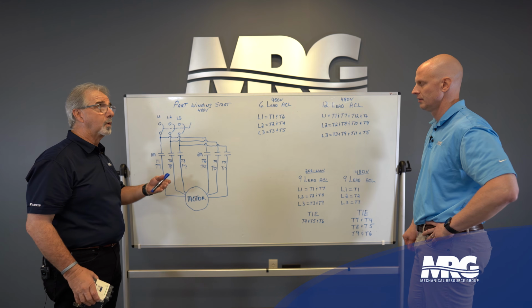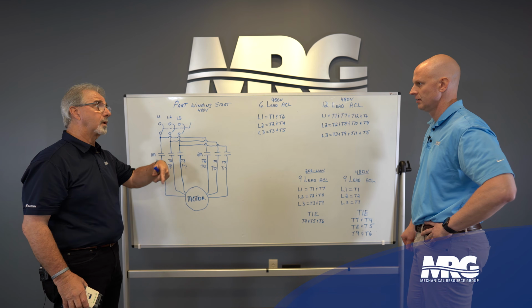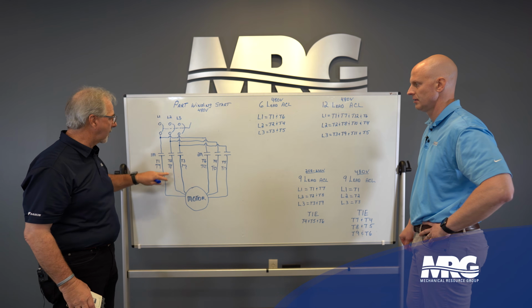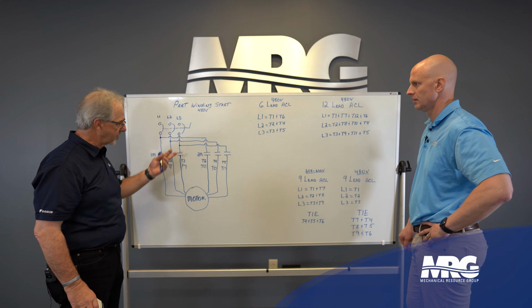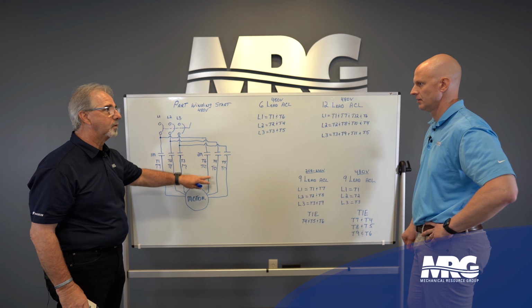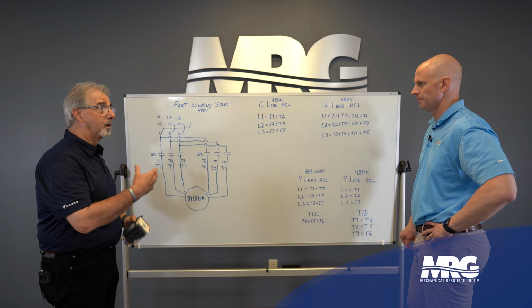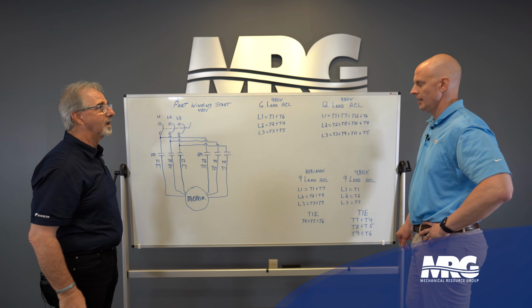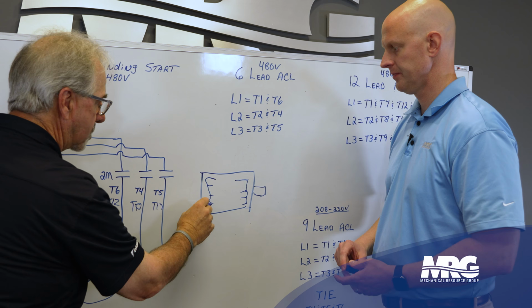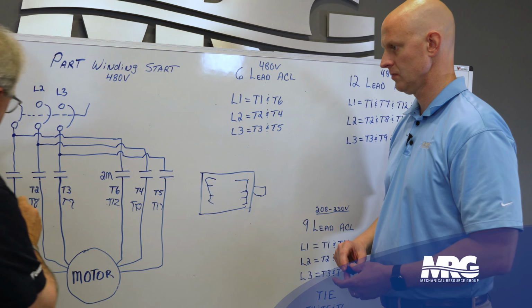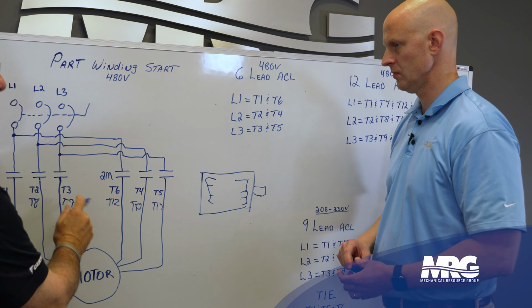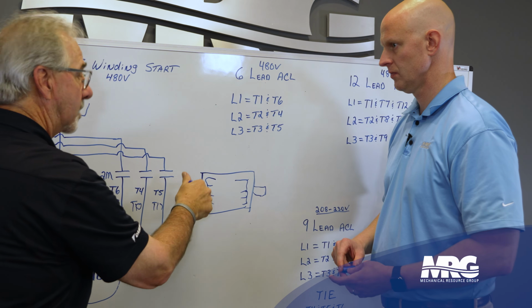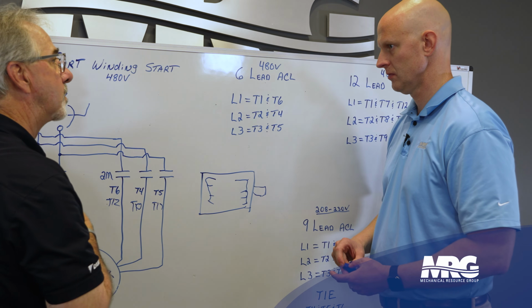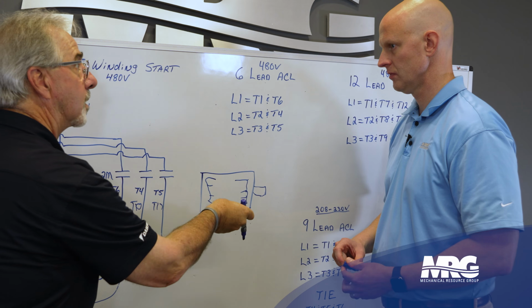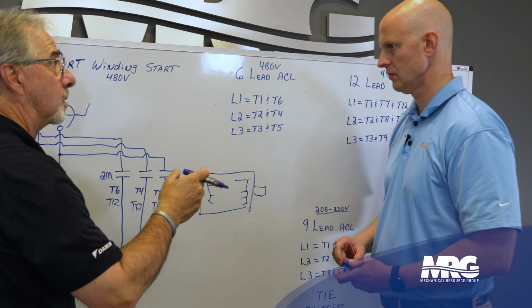Because the way a motor winding works, it has a series of coils. This is either side of one set of coils. Same thing with T6, T12, T4, T10. And if I was going to run it across the line, I would hook it up like that. So these connections you see here are these connections you see here. And those are all grouped together. Connections are made at what we call the crown, and then it comes out of the pecker head of the motor, and it numbers them 1, 2, all the way through 12.